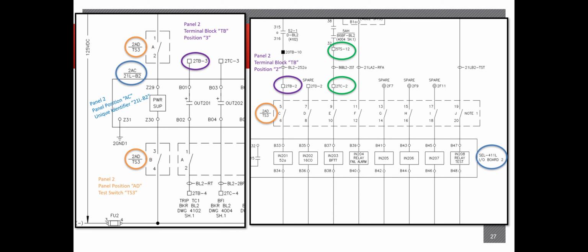We also have unique identifiers for terminal blocks that are not in the cabinet. The one below 2TC-2 will be in this cabinet. It's going to be marked panel 2, but you can see that again it actually has cabling leaving the cabinet and going to another panel, for example. It's actually going to be going to panel 5, and you can also identify that with the little cable number that runs in between those two circles, 86BL2-2ST. That little loop is pretty much just indicating that this isn't just a wire that's in the cabinet.